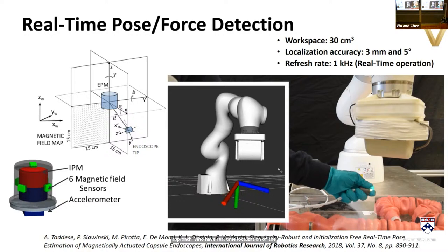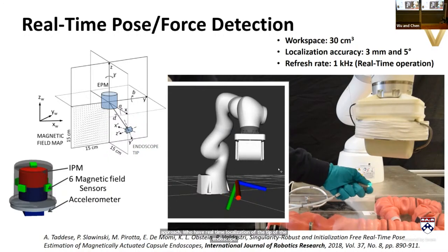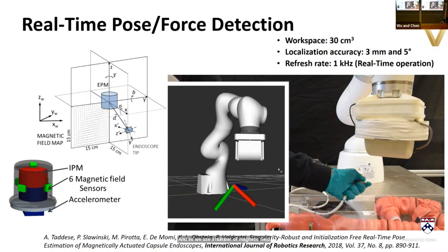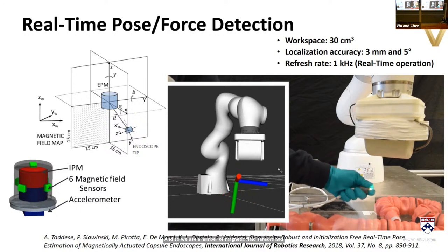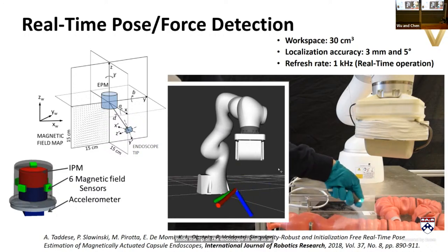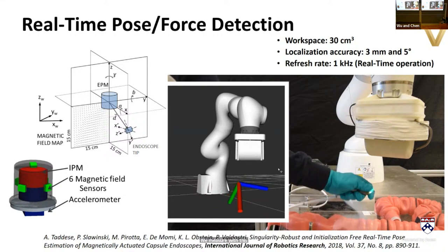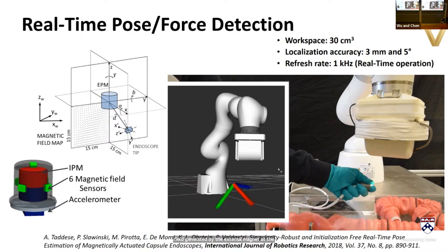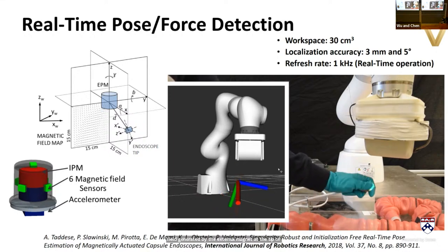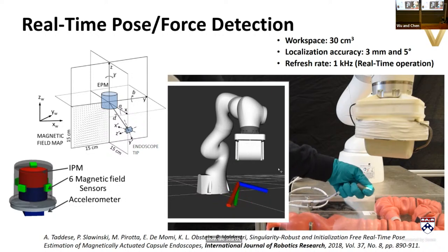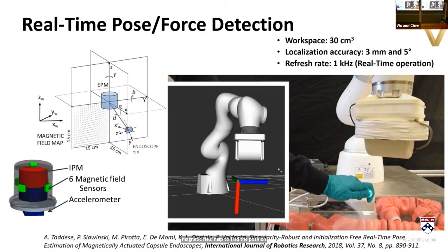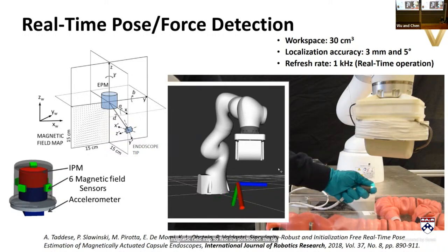We use a number of magnetic field sensors inside the tip of the endoscope, as well as an accelerometer. With these magnetic field sensors we measure the field generated by the external magnet at the tip of the endoscope, rotate it into the same reference frame as the external magnet thanks to the accelerometer information, and then perform a search in a pre-calculated magnetic field map to find the position the tip should be at to read that magnetic field.